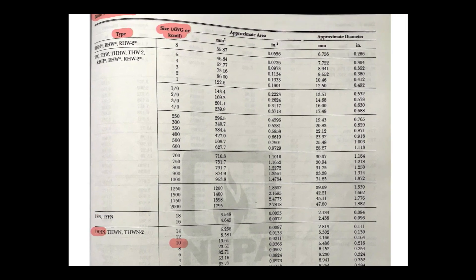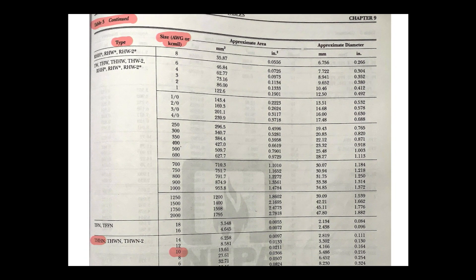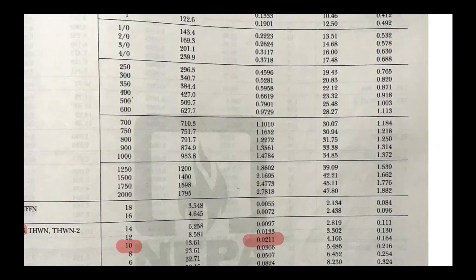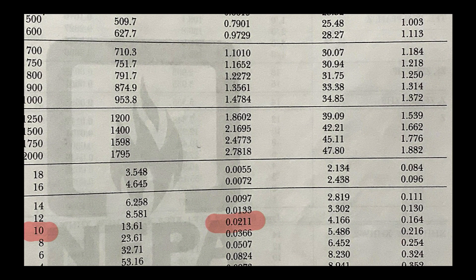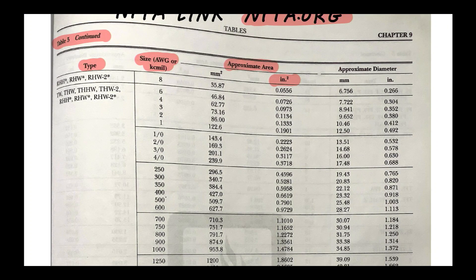I'll shrink this a bit so we can see the whole table. We're looking for the approximate area in square inches — not millimeters squared. If you pick up the millimeter numbers when the question asks for square inches, you'll get it wrong. Following across for THHN 10 AWG, we see the answer is 0.0211 square inches. Table 5 in Chapter 9 is a really important table.